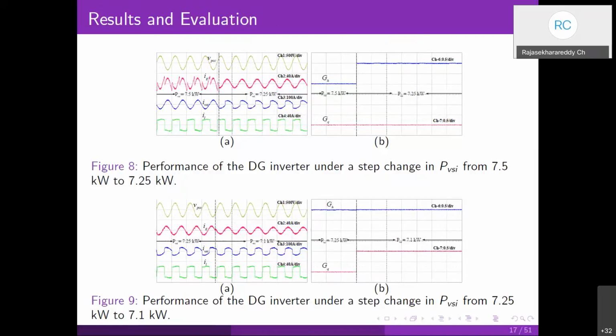As I said, in this first case in figure 8, the performance of the DG inverter under a step change in active power generation is demonstrated here. Here the voltage source inverter power is varying from 7.5 kilowatt to 7.25 kilowatt, so there is an active power generation change. Initially, the inverter is fully loaded by active power generation since its rating is 7.5 kVA, so it is fully loaded. And then this power drop has occurred. Active power generation has been reduced by 250 watts only.